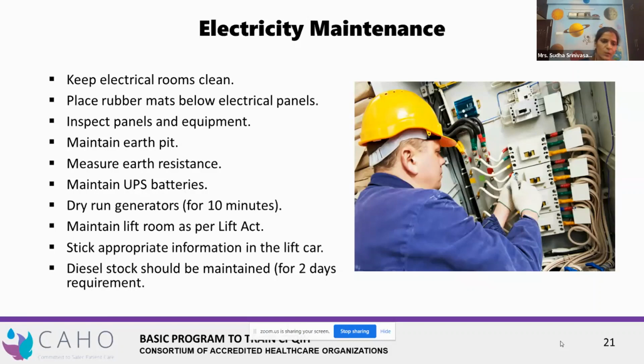The lift room, what are the requirements of the lift room? It should be easily accessible. There should not be any obstacle. There should be a telephone available in the lift room, which is on the terrace. Whether you have the fire extinguishers available in the lift room, the 11 kV rubber mats, whether you have the safety lever, whether the instructions are placed in a manner that the lift boy can understand. So these are very, very important.